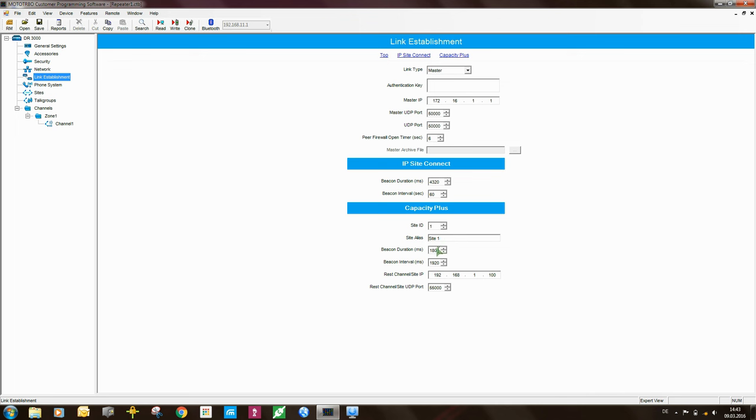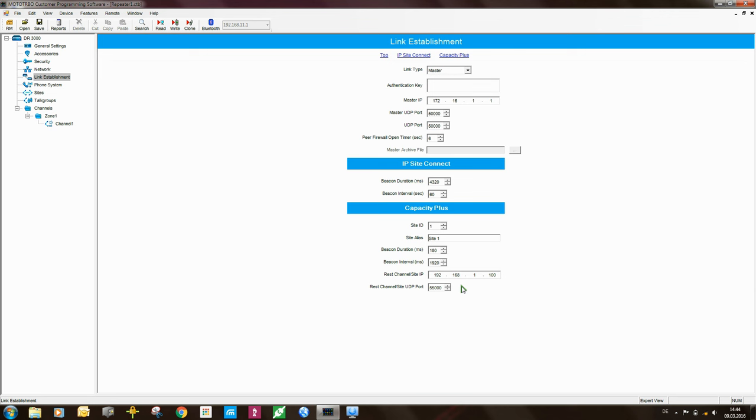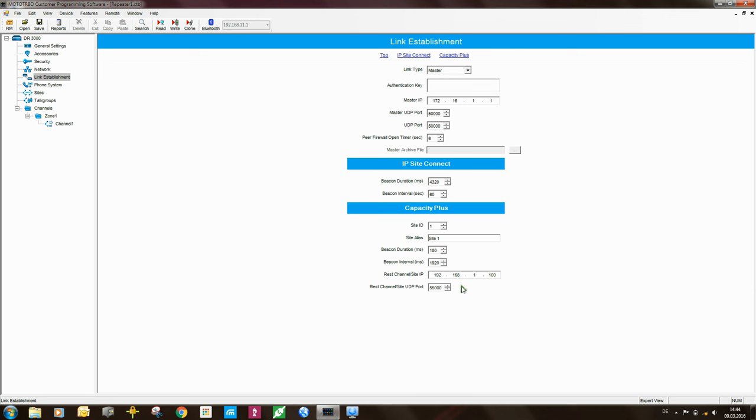The next two settings here, these are moderately important. This is the beacon duration and beacon interval. So when the repeater is acting as the rest channel, so one of the slots on this repeater is the rest channel, it will send out a beacon and the beacon in this case will be 180 milliseconds long and the beacon will be sent out every 1920 milliseconds. So when you set the repeater up for capacity plus or link capacity plus operation, as soon as the repeater goes into the rest channel mode, it will generate, you will see the TX light will pulse every roughly two seconds.